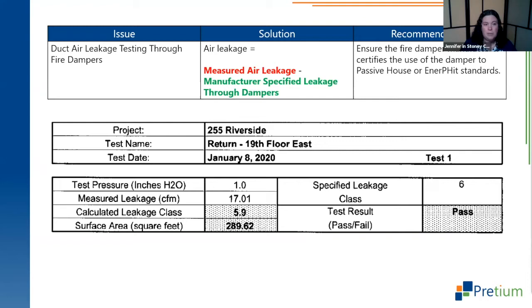Our solution ended up being that we took the measured air leakage of those duct runs and we subtracted the manufacturer specified leakage through the dampers, to basically try to remove whatever extraneous leakage we were going to be seeing as a result of things like the damper arm and some of the other penetrations that are required as part of the fire damper.